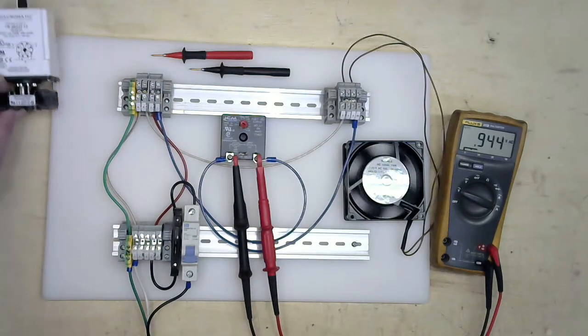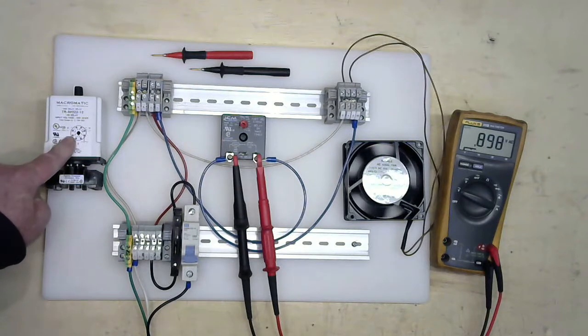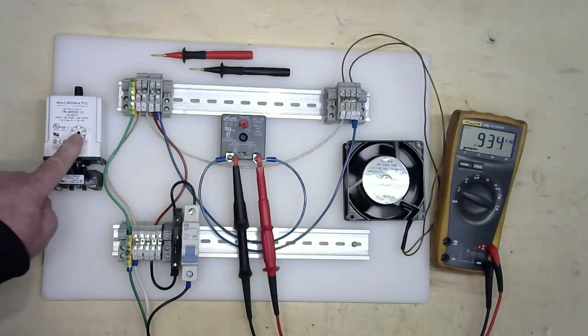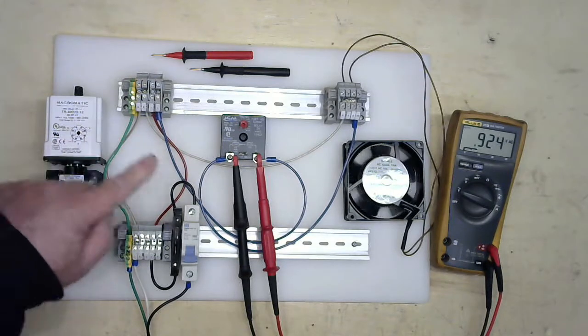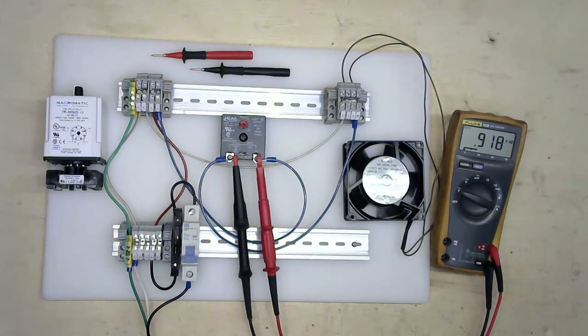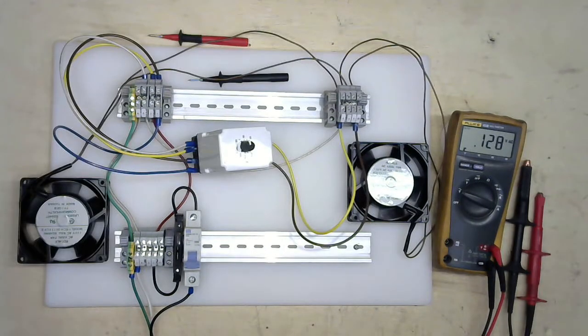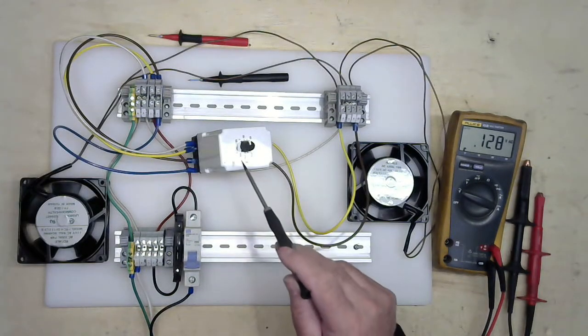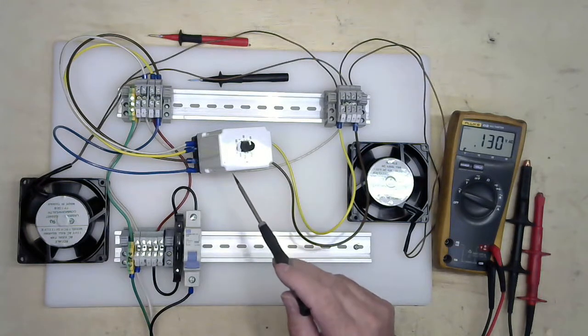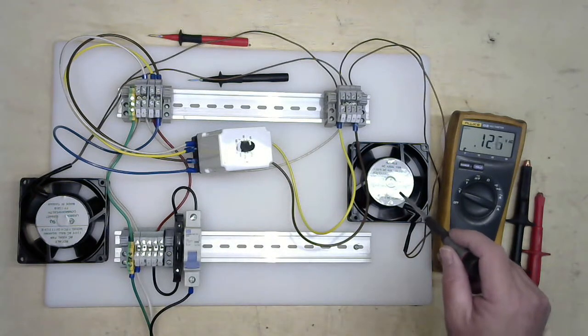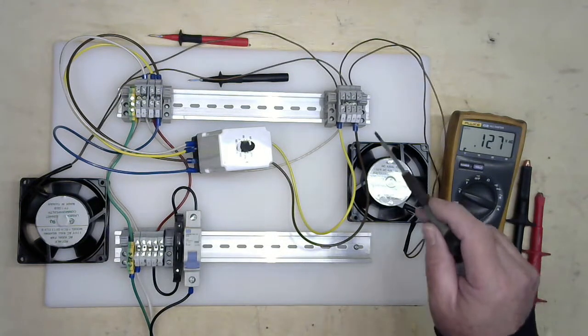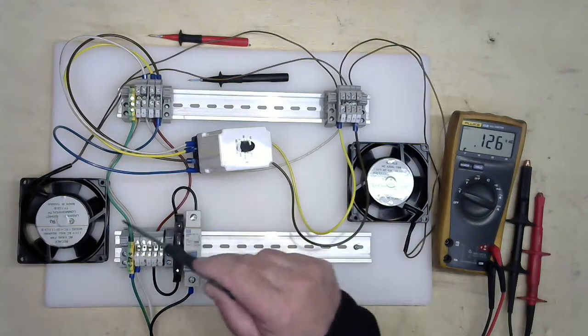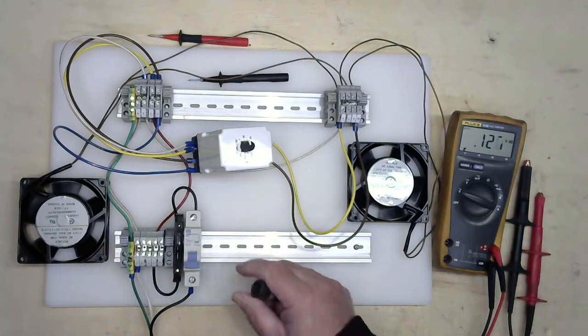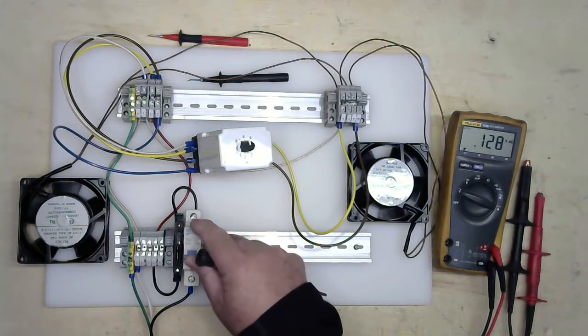In a minute, I'll demonstrate both contacts with you. We're going to do one set for a normally open and another set for normally closed. I'll be right back. Okay, now I have my time delay relay. It's adjustable. I have one fan set up as normally closed. When I apply power, this fan will come on. As soon as my timing times out, it will turn the second fan on. Let me give you a demonstration here.